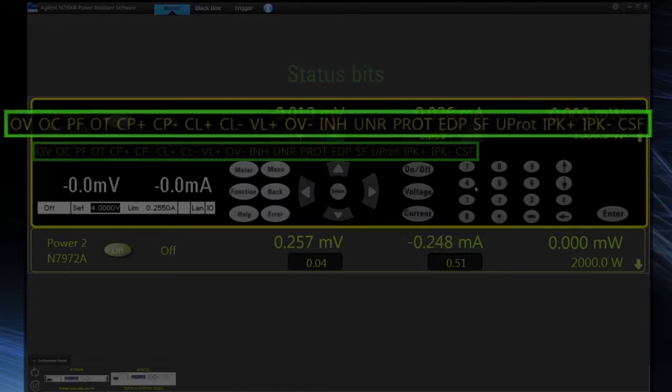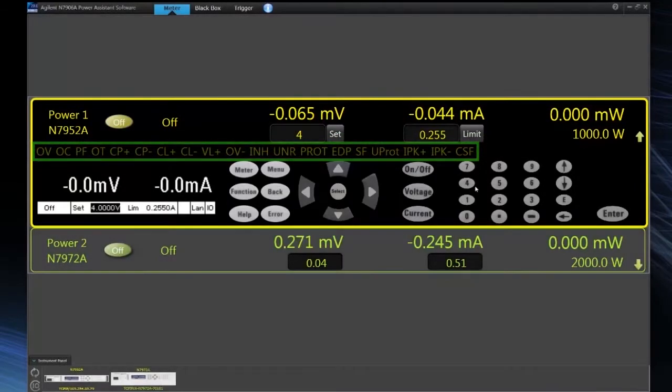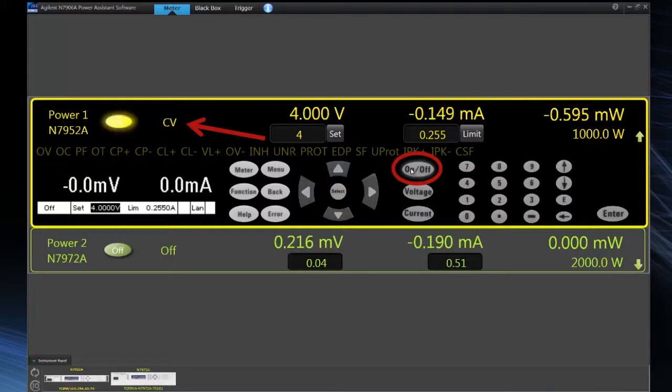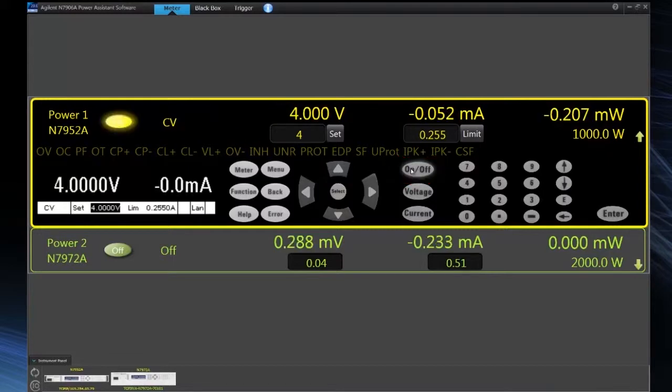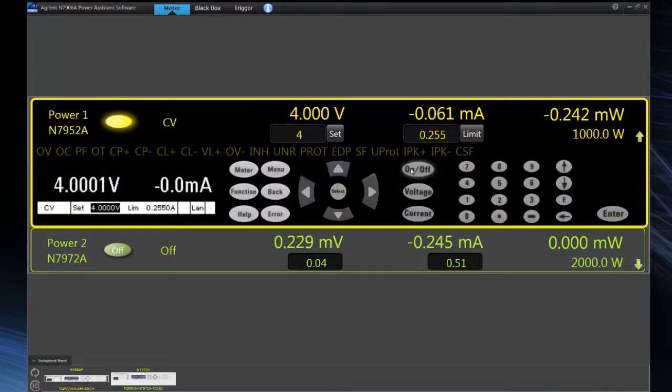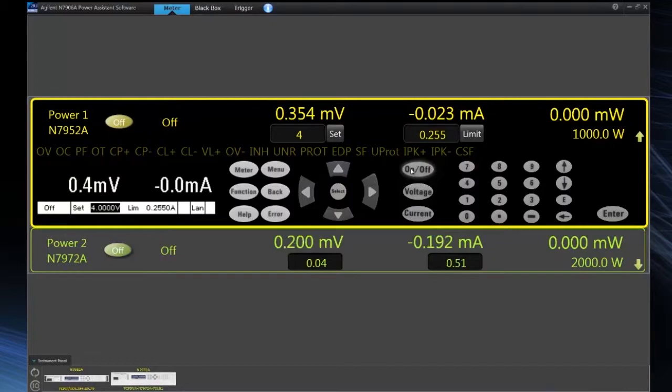We can see the status bits such as over voltage and over current. We also have access to all the front panel controls. So for instance, I could turn the output on and we can read back the resulting output voltage and current. So right now we're set for four volts, and then I can of course turn the output back off. So we have all the controls on the front panel.